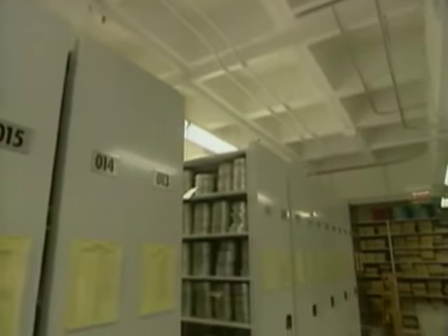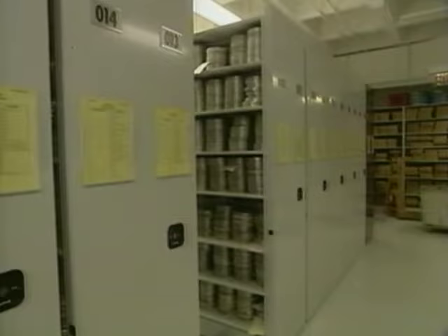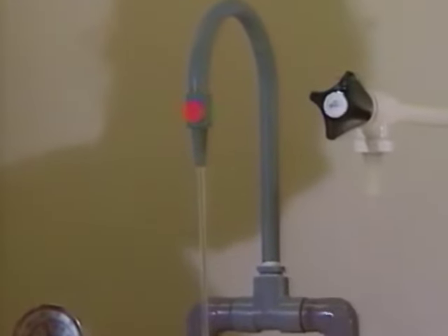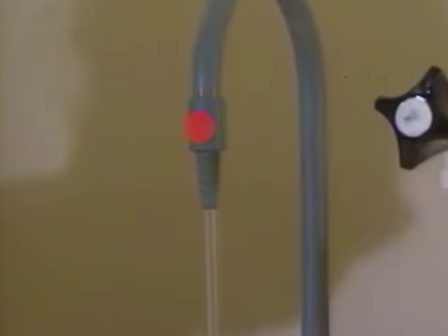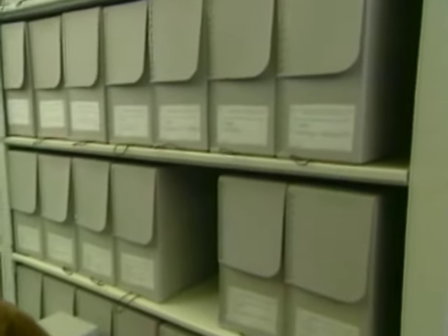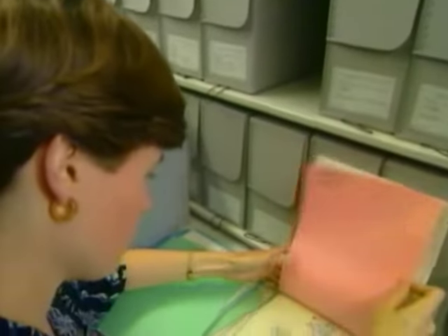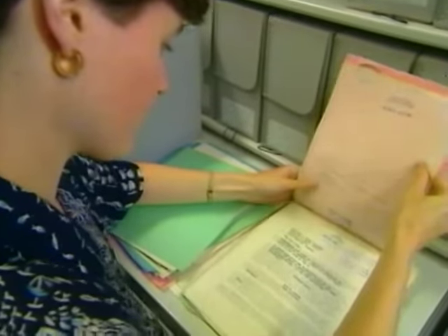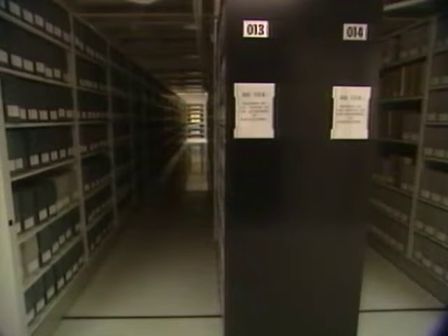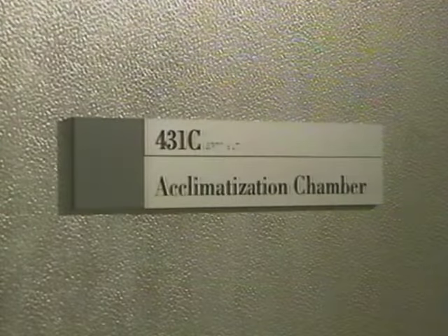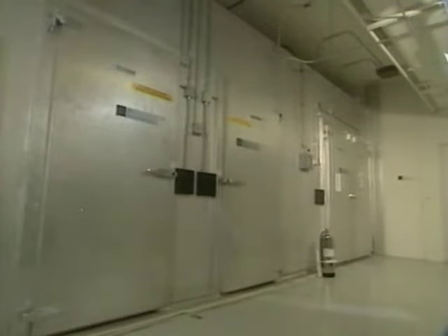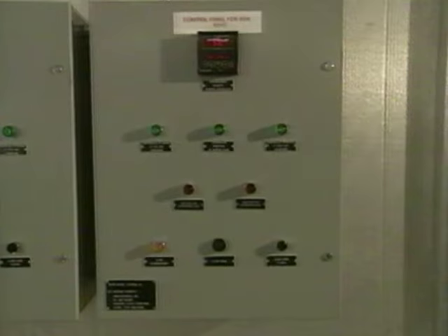The two significant mechanical systems in the building deal with the HVAC systems for the record storage areas and the deionized water systems devoted to laboratories in the building. The stack areas are designed to accommodate the media stored within them. For example, the textual records are designed to accommodate paper-based records and are stored in an environment requiring 70 degree temperature and 45% relative humidity. At the other extreme, we have cold storage vaults, which are designed to accommodate color film and are designed for 25 degrees and 30% relative humidity.